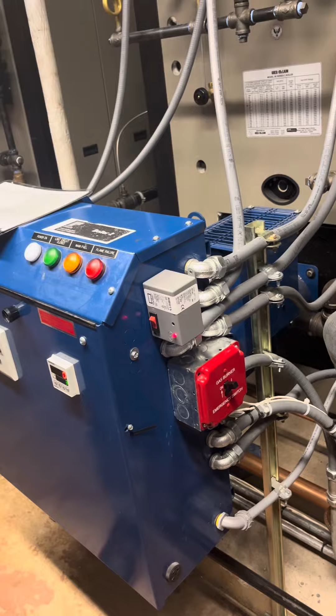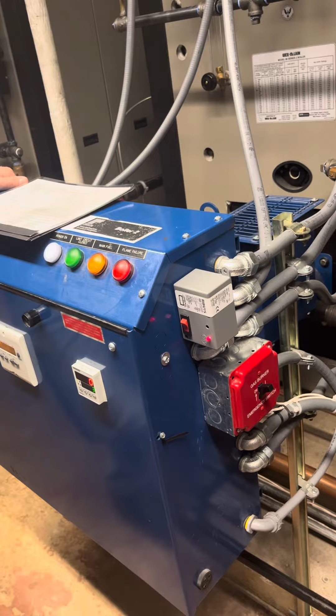And I come in here, and as soon as I release all the overrides you put in the system and let everything sit for a few minutes and turn it back on, magically it works exactly the way it was intended to. So the more overrides you put in the system, the more times you're messing with things and overriding everything, the more problems you cause, because the system can't operate the way it was intended to.